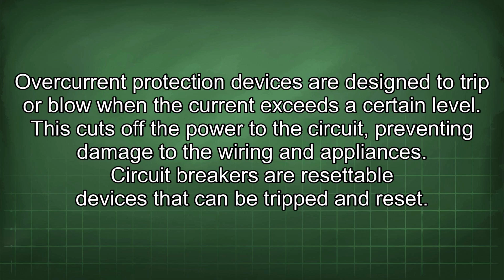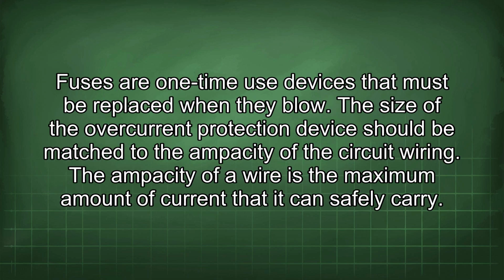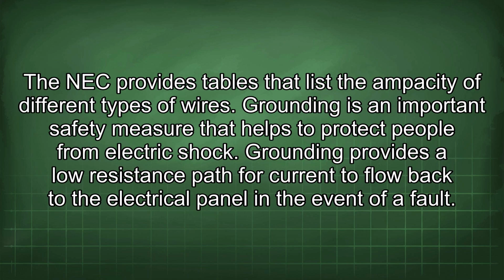Circuit breakers are resettable devices that can be tripped and reset. Fuses are one-time use devices that must be replaced when they blow. The size of the overcurrent protection device should be matched to the ampacity of the circuit wiring. The ampacity of a wire is the maximum amount of current that it can safely carry. The NEC provides tables that list the ampacity of different types of wires.